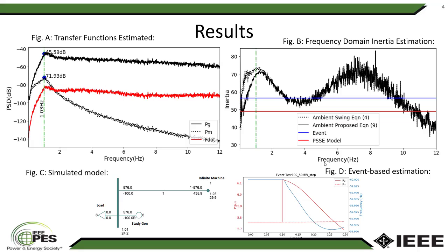And for reference, we created a step change at this generator of 50 megawatt, and we have plotted the inertia estimate or inertia constant, which is given by the blue line. And you can see how the inertial response changes a lot. So depending on how fast the disturbance is, the estimated inertia value could be totally different. And this is why you need an inertial response as opposed to a constant parameter value.